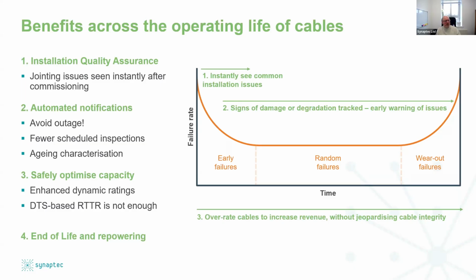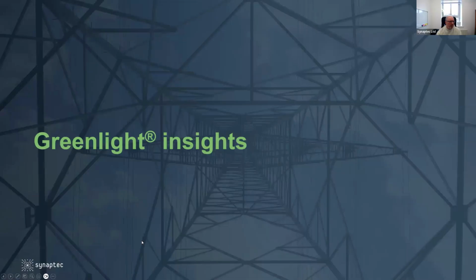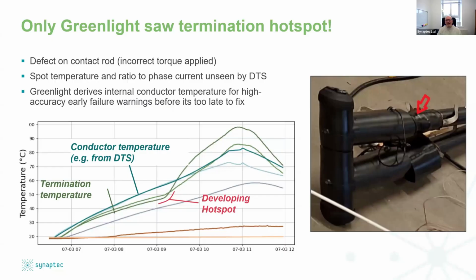And then, of course, optimization of capacity. This is not true for everyone, but there are occasions where you need to overrate cables and deliver more power at a certain time for short periods of time. And we've noticed that dynamic rating is incomplete without this technology. We'll show an example of why. And so sometimes when people specify DTS alone for what they call real-time thermal rating or dynamic rating, it's actually not enough. And we'll give you an example of that in a moment.